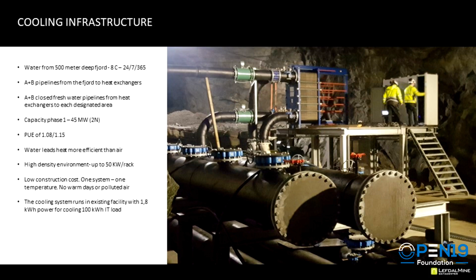I'm not sure if everyone in the room knows, but water is a very effective cooling medium. It leads heat about 4,000 times more efficient than air. So by using cold water in our solutions, we can have up to 50 kilowatt per rack. Now, if you run a regular solution of 5 kilowatt per rack, and that's very cost efficient, you can imagine what happens when you increase the density in the same footprint.